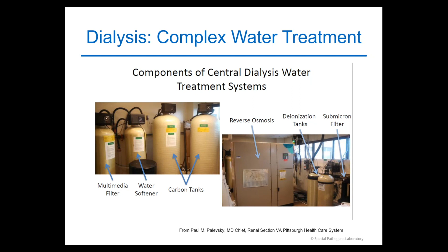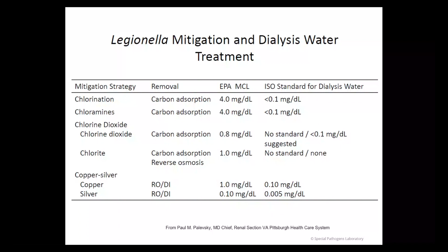This table shows you the common disinfectant strategies: chlorine, monochloramine, chlorine dioxide, the presence of chlorite in the water because of chlorine dioxide, and copper-silver ionization. Most of the time, the carbon adsorption filter removes them, or in the case of chlorite, the reverse osmosis does, and also for copper-silver. It has the estimated EPA limits for those disinfectants, and what the ISO standard says should be in the dialysis water. So just keep that in mind, especially if monochloramine is used. You need to have high vigilance about the treatment of dialysis water.